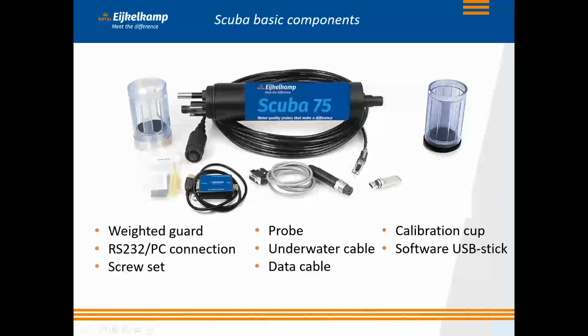There's also a calibration cup - this is the right one. If you want to calibrate the probe, just put the probe with the sensors on top, put on the calibration cup, remove the black cover on top, and then you have an open space to the sensors where you can put in the calibration fluid.